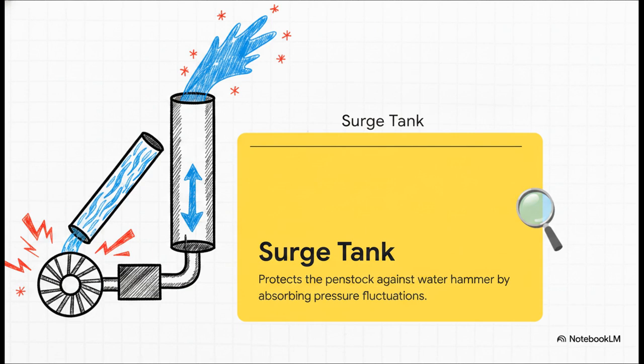Moving further along, we find the forebay tank and the surge tank, which, honestly, solve a massive engineering problem. Just think about it for a second. You've got thousands of tons of water rushing downward. If the turbine's electrical load suddenly drops and the valves have to close quickly, well, all that water still has to go somewhere. The surge tank absorbs that violent pressure spike, a phenomenon known as water hammer, by giving the water a place to safely surge upwards. It effectively stops those massive pipes from literally bursting under the strain.